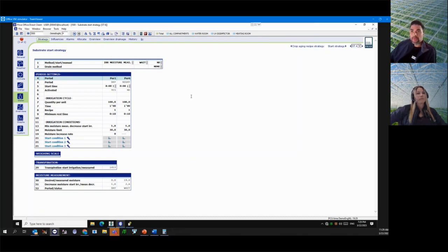For us to use a sensor, it needs to be a standard universal output, like a 0 to 5 volt signal or a 4 to 20 milliamp signal. So those are universal sensors, and we can calibrate those a certain way. But if it's a communication protocol, like a lot of Grodan sensors I've seen, which are SDI-12, there has to be a special converter.